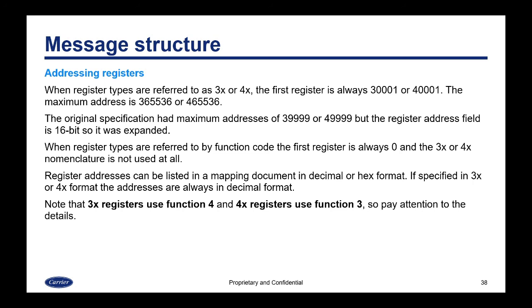When register types are referred to by function code, the first register is always 0 and the 3x or 4x nomenclature is not used at all. This is a big deal with Modbus — do you start the addressing at 0 or 1? If it is referred to starting at 0, or using the function code, you will start at 0. Register addresses can be listed in a mapping document in decimal or hexadecimal format. If specified in 3x or 4x format, addresses are always in decimal format — so the address would list as 40001 instead of as 0.